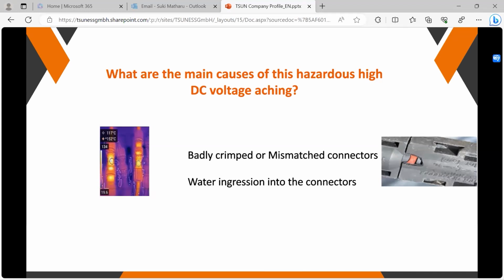You can see the connector on the right-hand side here. It's got a slight micro crack in there, and that crack becomes a problem for water ingression. You probably get water going into that, and eventually at some point that could become an issue. Again, as I said, the higher the DC, the worse that problem will be, and we need to avoid that at every cost possible.